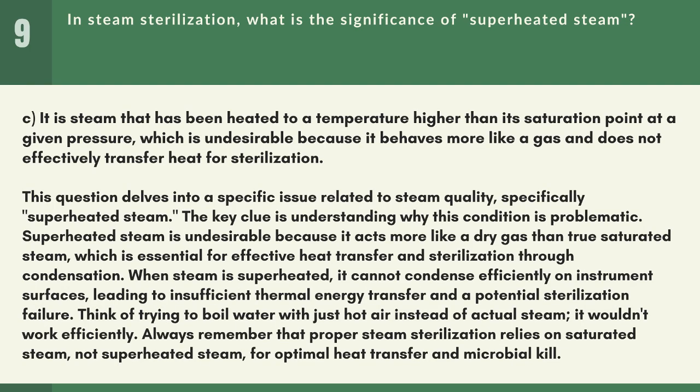Answer: C. It is steam that has been heated to a temperature higher than its saturation point at a given pressure, which is undesirable because it behaves more like a gas and does not effectively transfer heat for sterilization. This question delves into a specific issue related to steam quality, specifically superheated steam. The key clue is understanding why this condition is problematic.